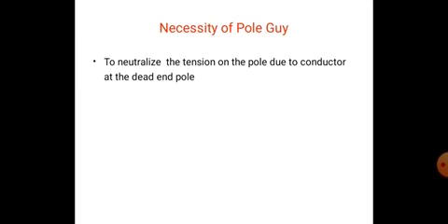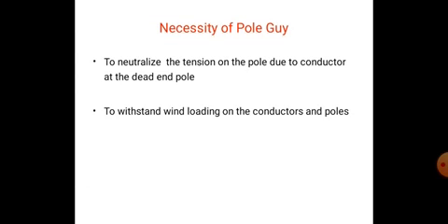What is the necessity of pole guy or pole stay? To neutralize the tension on the pole due to conductor at the dead end pole. To withstand wind loading on the conductors and poles. To keep the pole straight without bending.